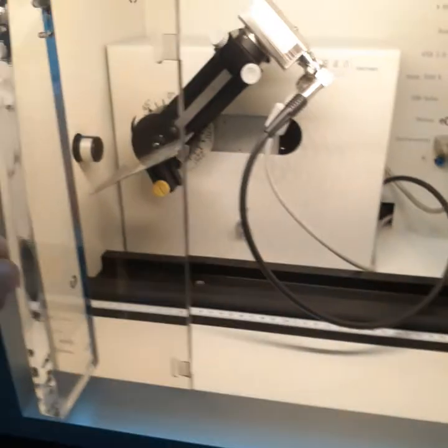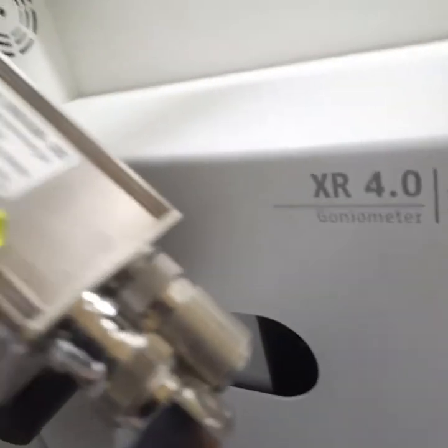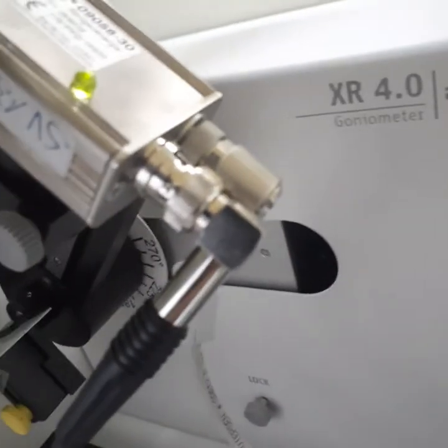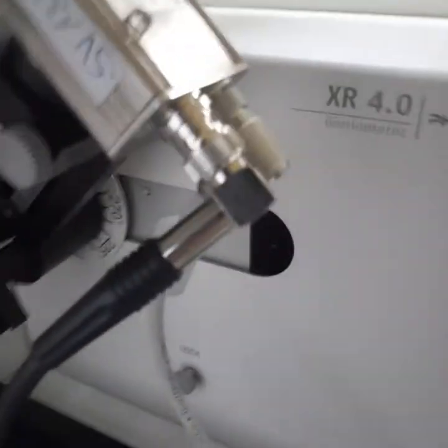Now we would like to close this window and turn off the light to make sure that the solid state detector is already on. It is green now. If we turn off the multi-channel analyzer, then it will turn off here once again. Then let's go back and turn on the multi-channel analyzer. Now the detector is on.